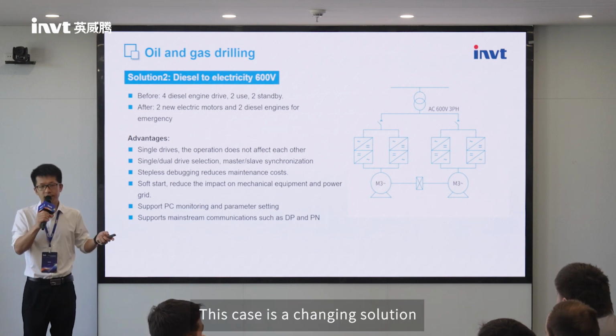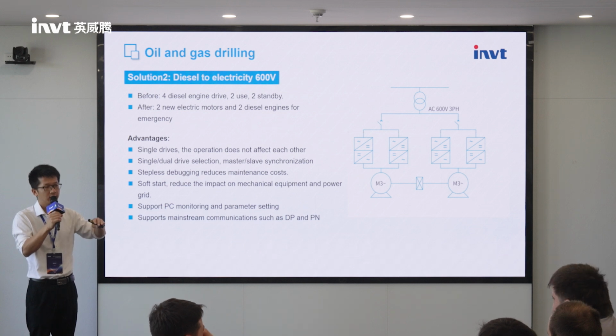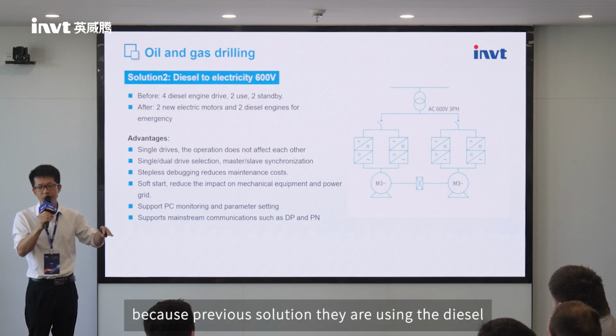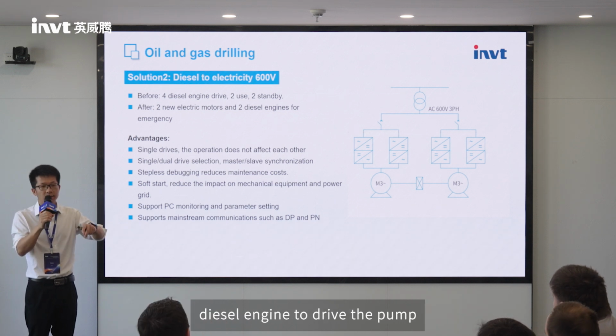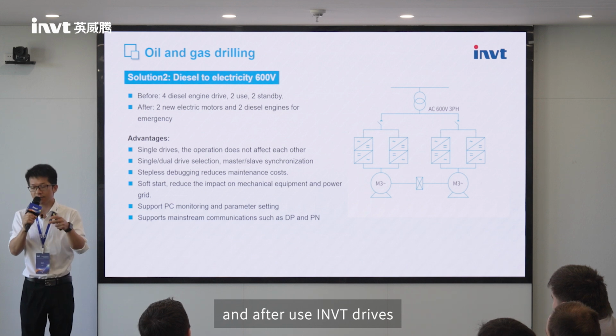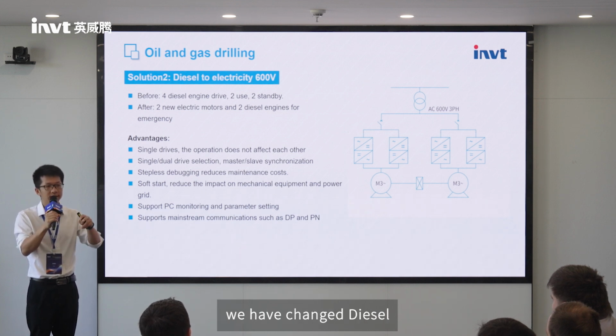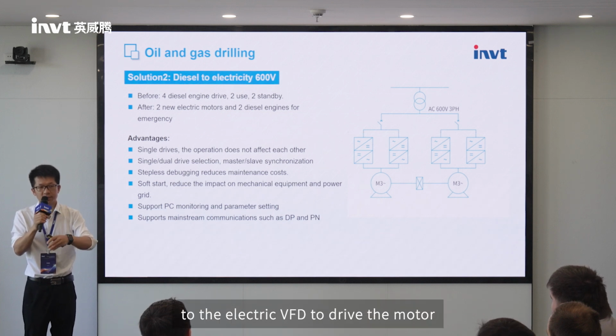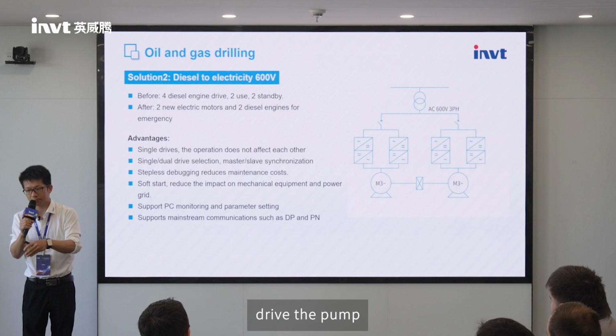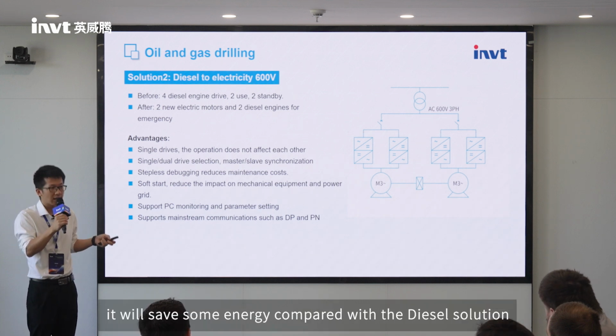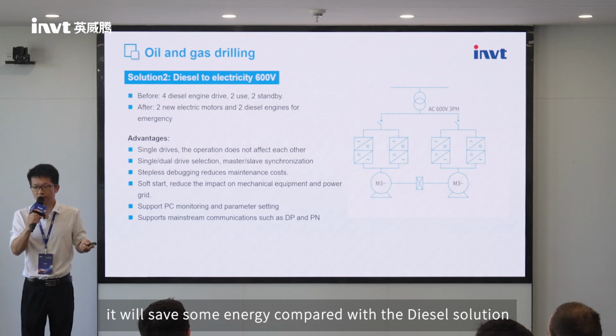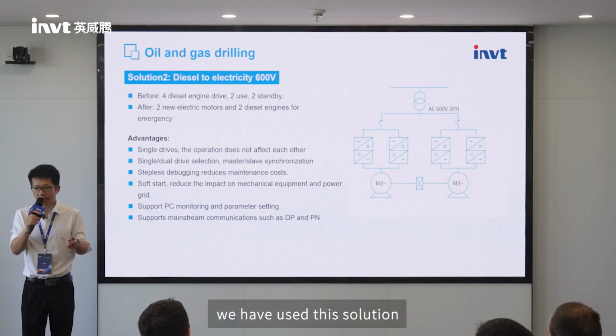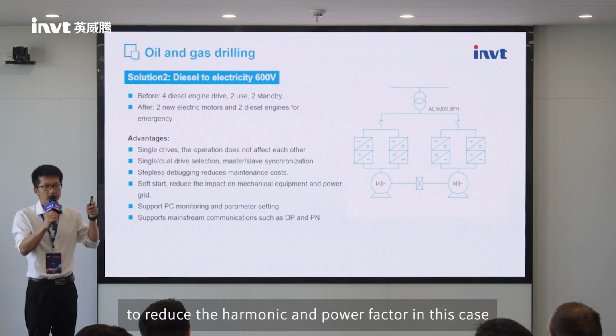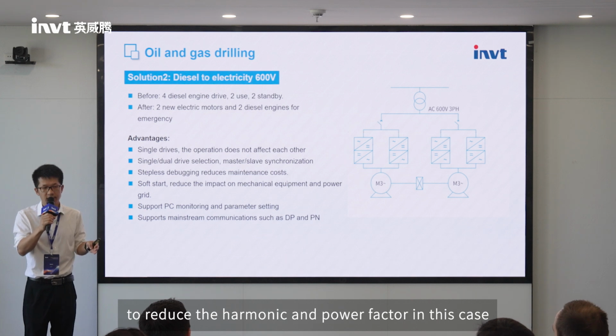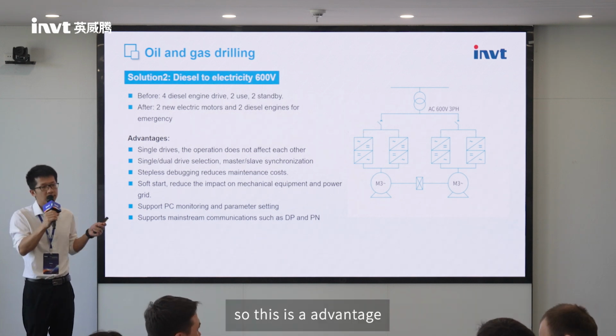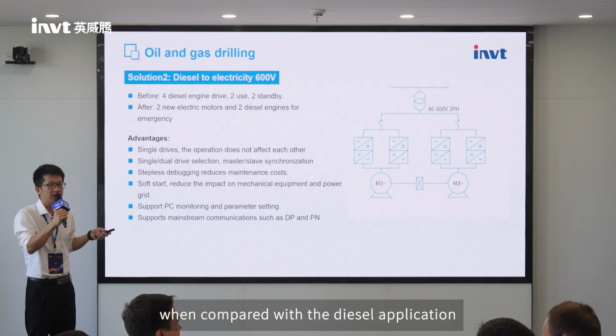This case is about changing the previous solution, because the previous solution used a diesel engine to drive the pump. After using INVT drives, we changed from diesel to an electric VFD to drive the motor and pump. This saves energy compared with the diesel application. We've also used this application to reduce harmonics and improve the power factor.